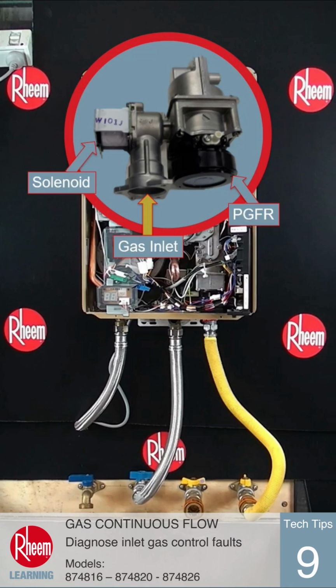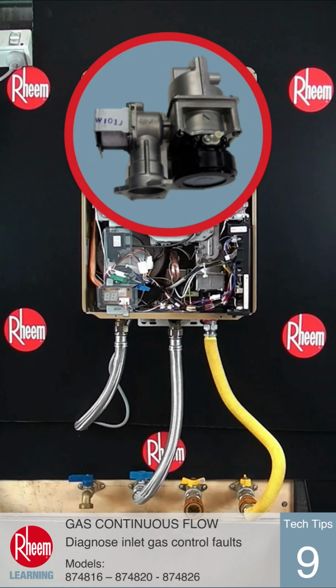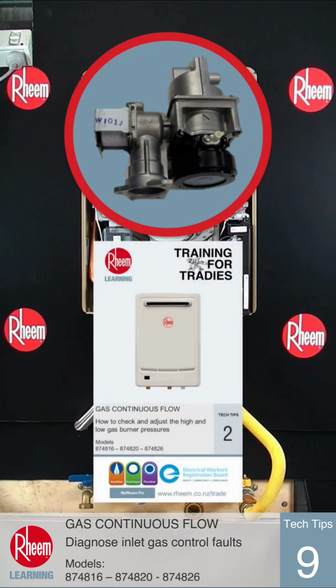If this valve develops a fault, either no gas will flow or the burner pressure would be incorrect, leading to error code 11 and 12, and also poor water heater performance if the burner pressure is low. Any faults relating to gas supply to the burner should always begin with checking the inlet working pressure and also checking the high and low burner pressure settings. This is set out in Tech Tips number 2.